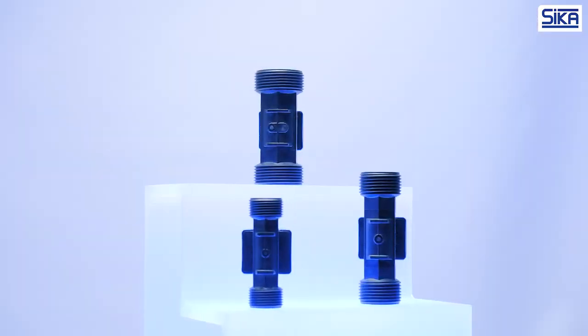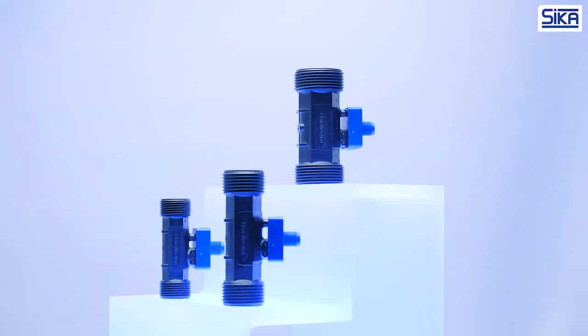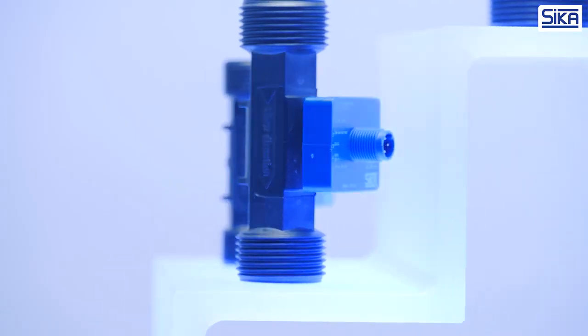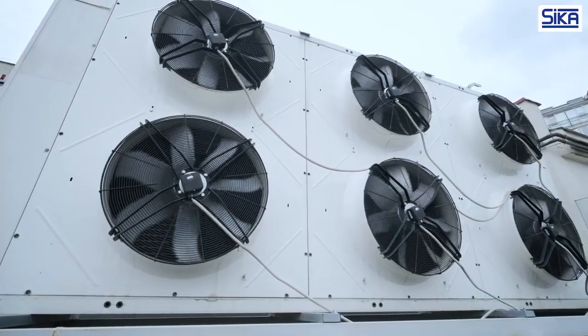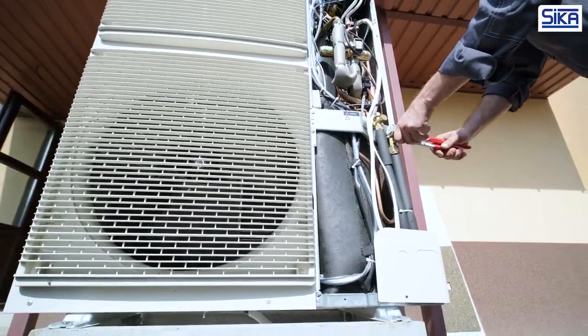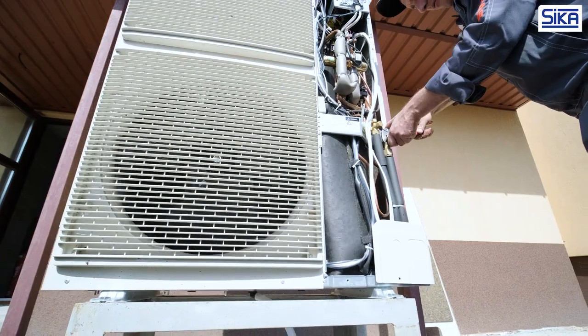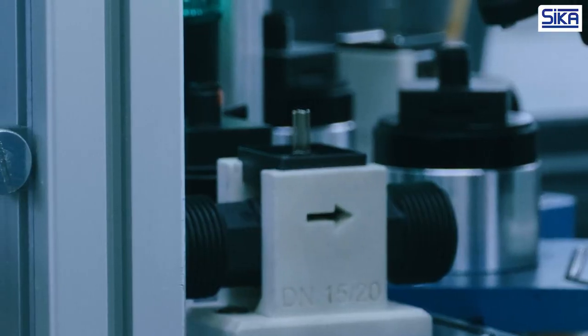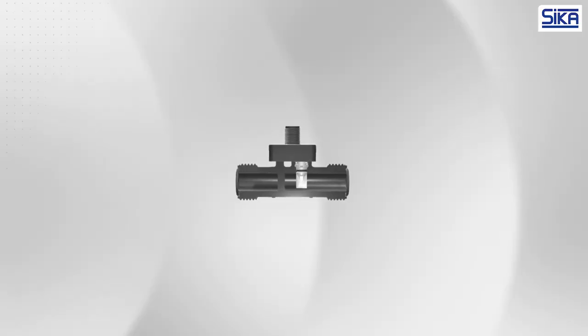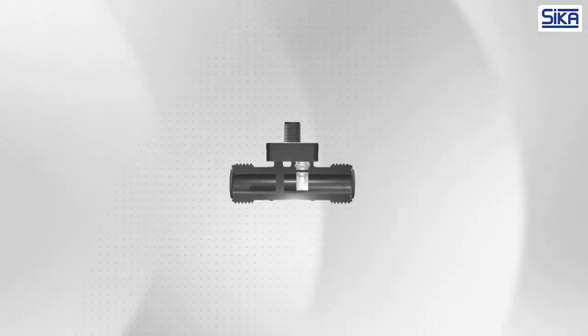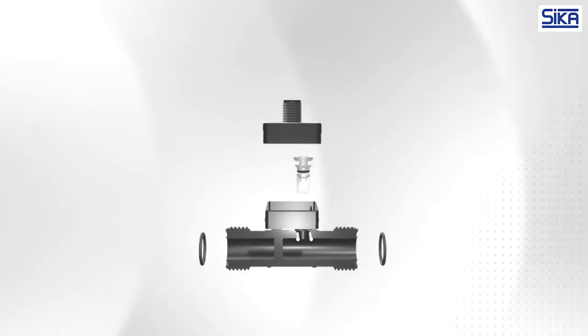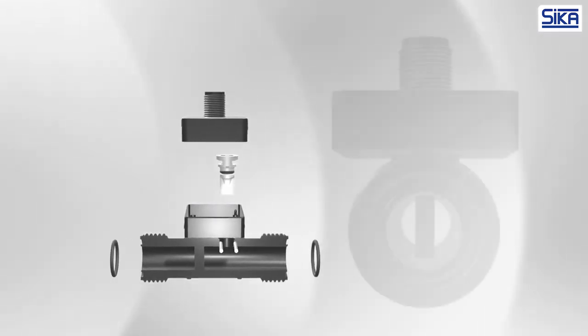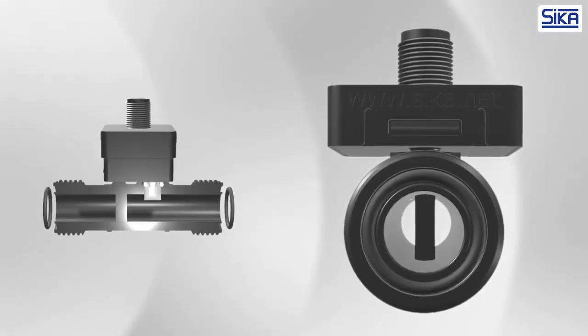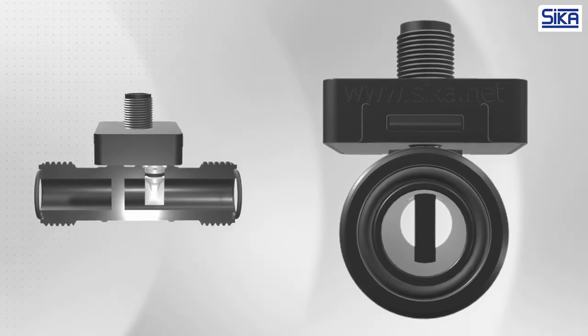Vortex flow sensors are an integral part of modern flow measuring instruments. Their advantages make them a key component in the increasingly important heat pump market. There are crucial reasons for this. They are inexpensive to manufacture and can be produced inexpensively in very high quantities. They have no moving parts, which promises long-lasting, trouble-free operation. And they exhibit very low pressure drops since the pipe cross-section is completely open aside from the bluff body.